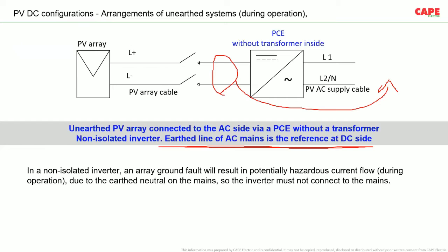Earthed line of AC mains is the reference at the DC side. The first safety measure you should understand is never try to earth this neutral. Never connect this neutral to earth, which I have often seen in several places. The neutral terminal of the inverter connected to earth is a big violation of the safety measure. Please don't do it.